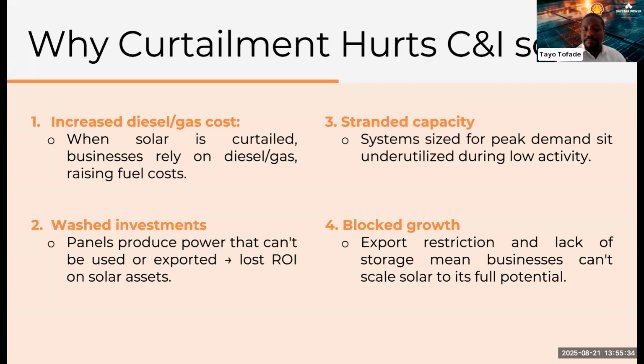Thank you, Shankaransh. I think the biggest impact is cost. Where we own the gensets, for example, and we're curtailed based on load demand, we see increased diesel or gas cost—so increased fuel cost. This is because with curtailment, the gensets run at their base load, and multiple gensets are running. That's purely diesel cost in terms of fuel, but also from a maintenance perspective, they're running more, and of course the assets are depreciating too. So we see increased cost in general.